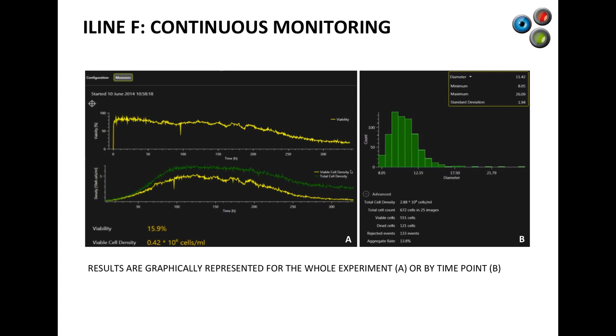We also have access to data such as the average cell diameter, the cell size, the cell optical height, and the cell volume. This is the microscope, a specifically adapted microscope for the online cell monitoring application. It does cell count, viability, morphology, and measures aggregates, and in the future it will be able to be used to predict optimal harvest times for the cells. The analysis time is very fast, and we acquire holograms, as I said, every 30 minutes, but that is a software parameter, so it can be configured.